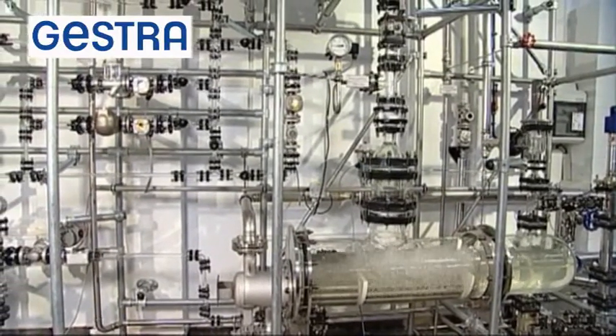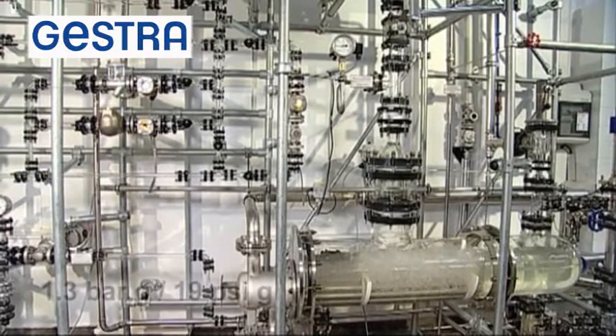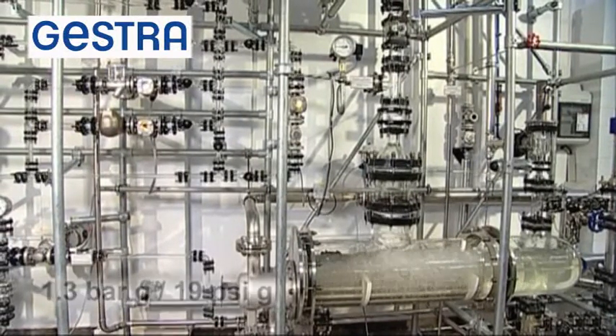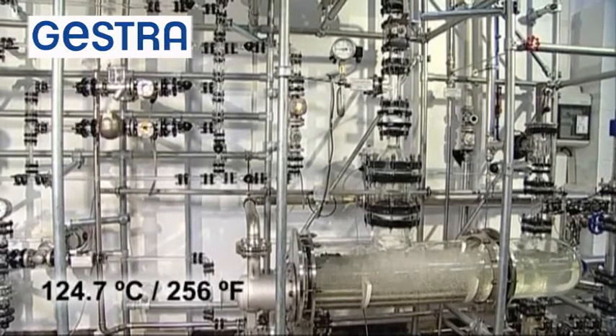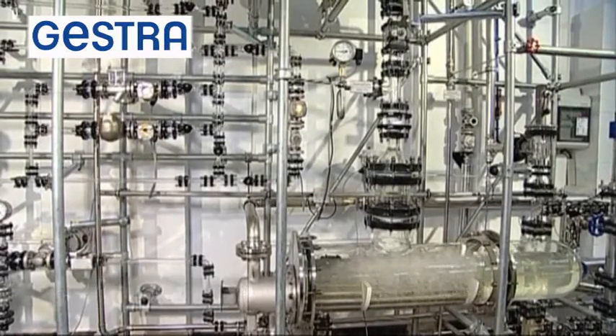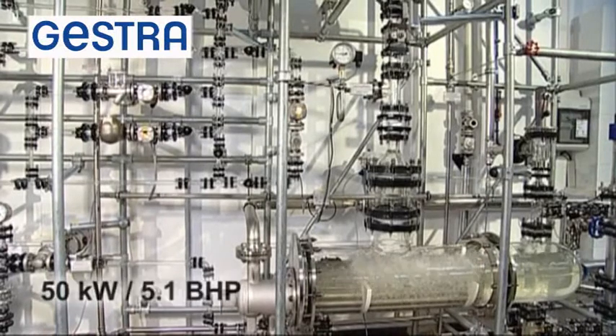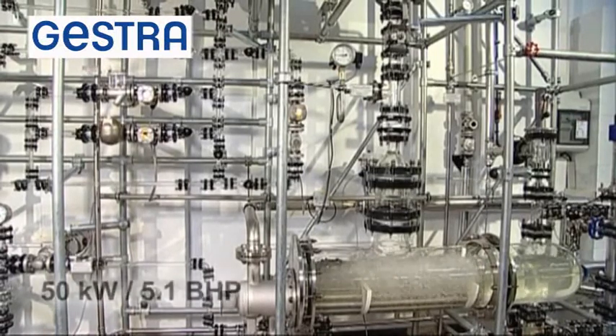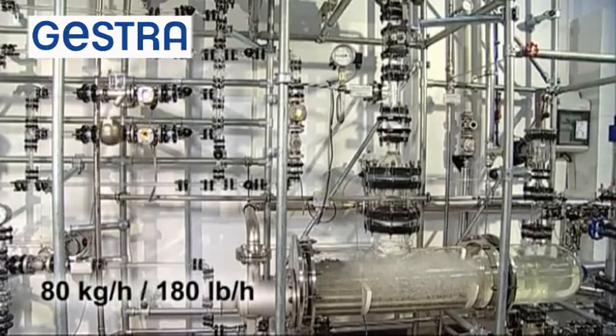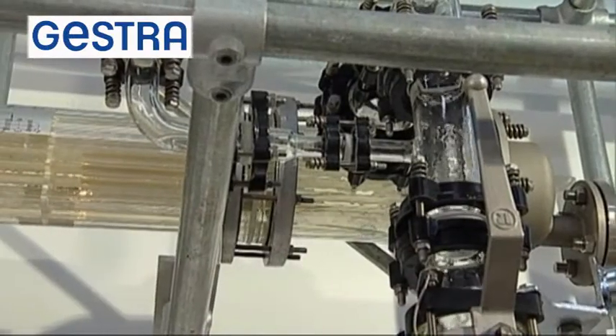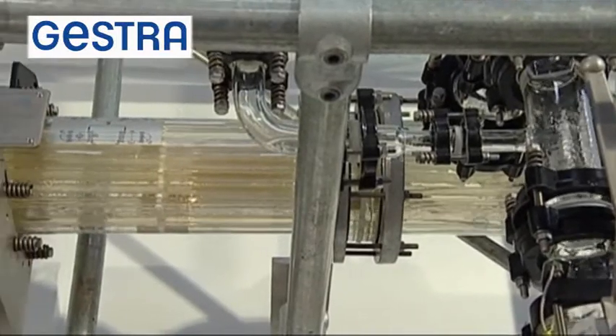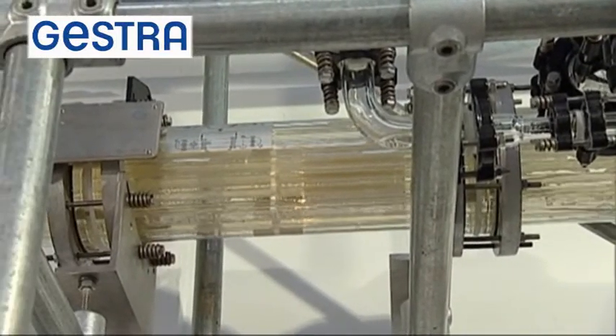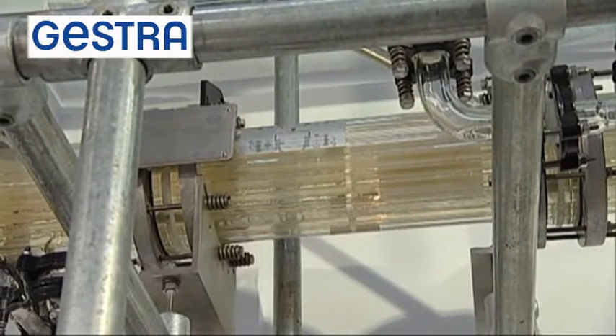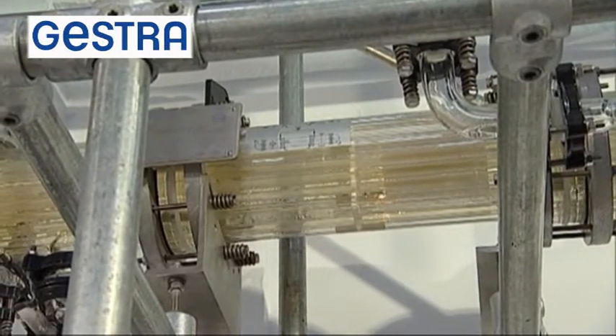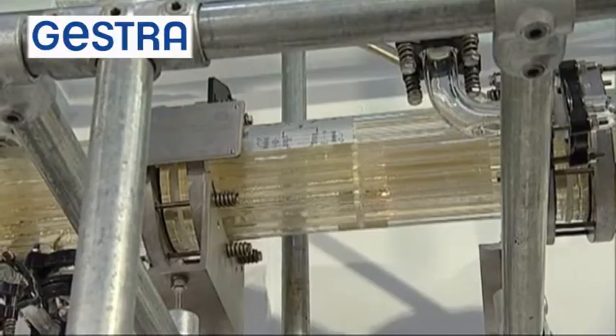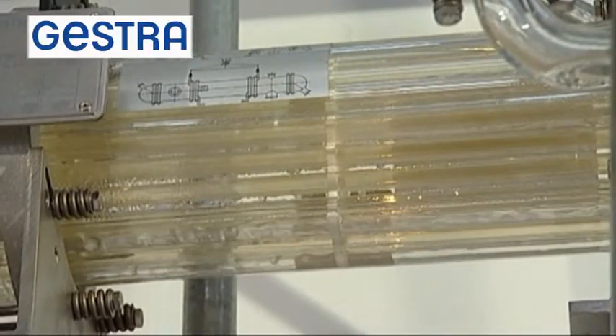The steam system consists of a secondary steam generator with a service pressure of 1.3 bar G, corresponding to a saturation temperature of 124.7 degrees centigrade. The capacity of the steam boiler is 50 kilowatts, which yields a steam flow rate of 80 kilograms per hour. As the condenser, we're using a glass heat exchanger mounted above the steam generator. As the coolant, tap water is used. The cooling water flows in the tubes, while the steam flows in the jacket around the tubes.